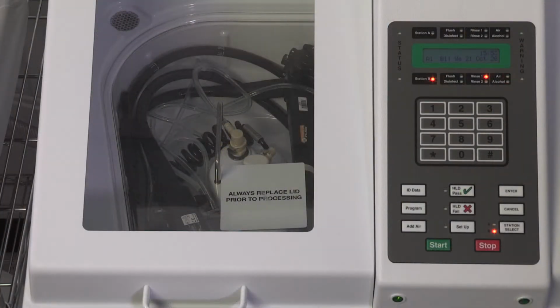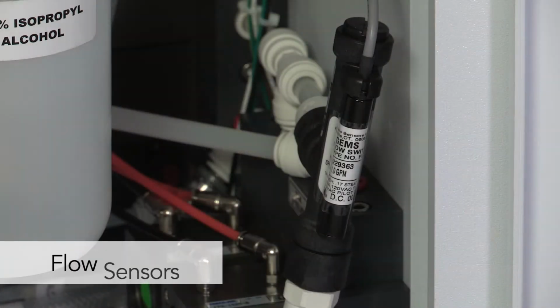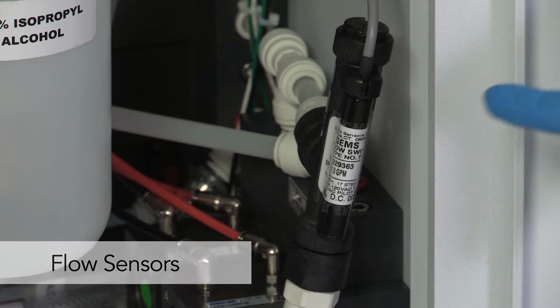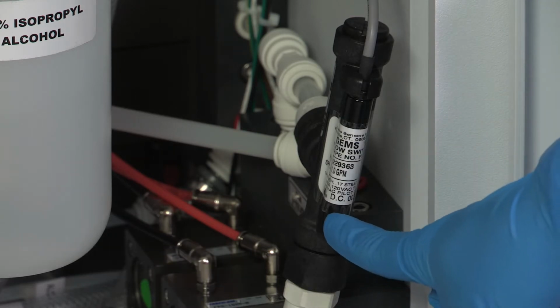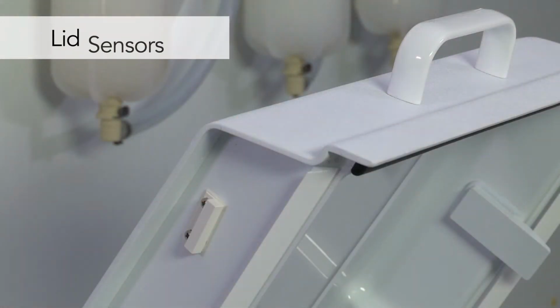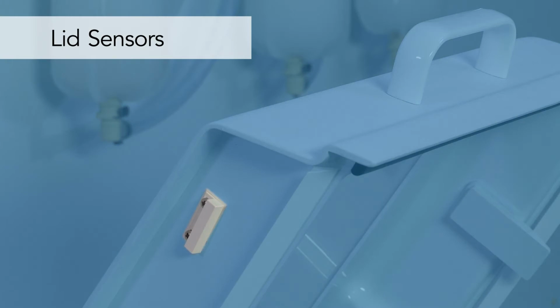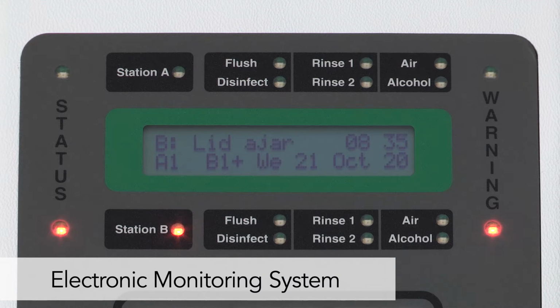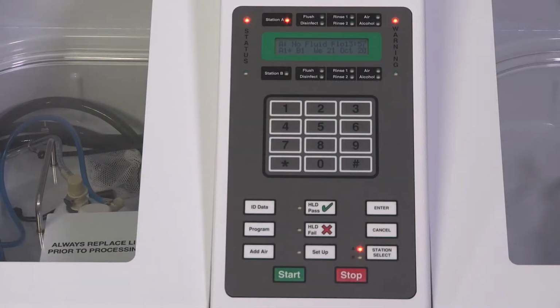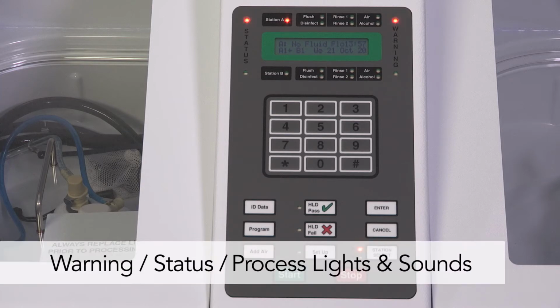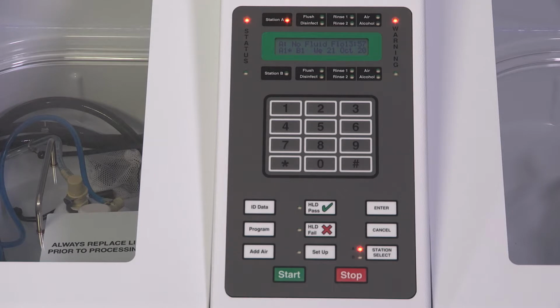The DSD EDGE Reprocessor includes a sensor package and safety features. Let's take a look. Flow sensors ensure flow from the AER through the hookup connected to the endoscope channels. Lid sensors alert operators if the lid is open or ajar. An electronic monitoring system alerts you to a condition that requires attention. Safety features also include warning, status, and process indicator lights and audible tone.